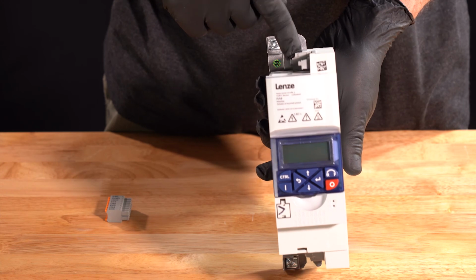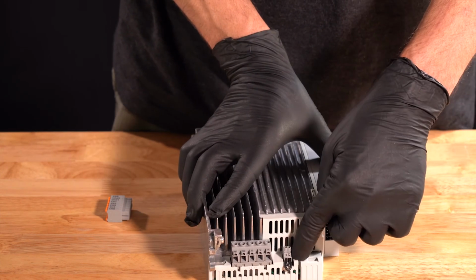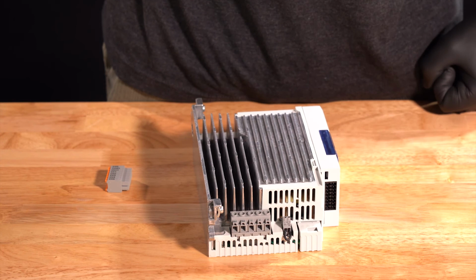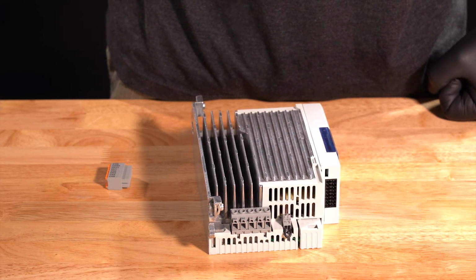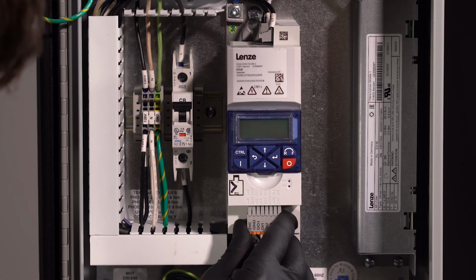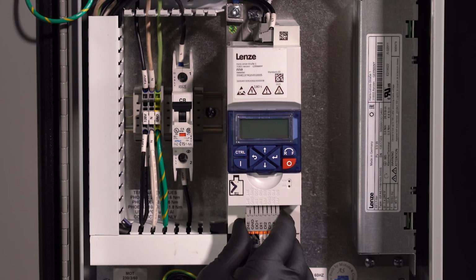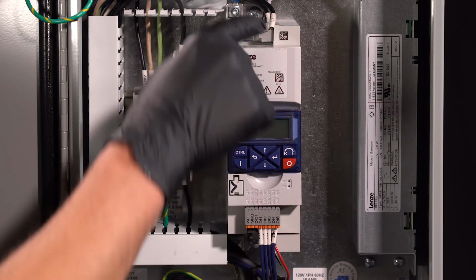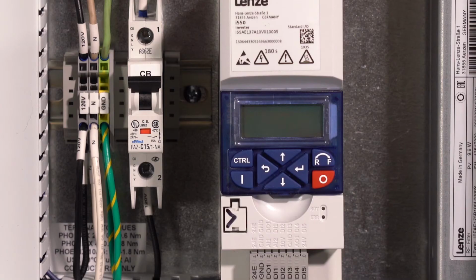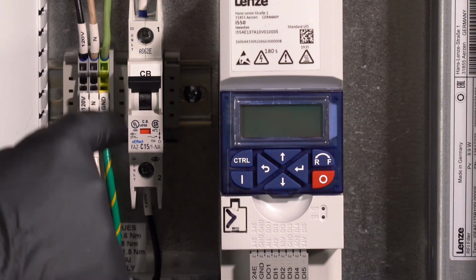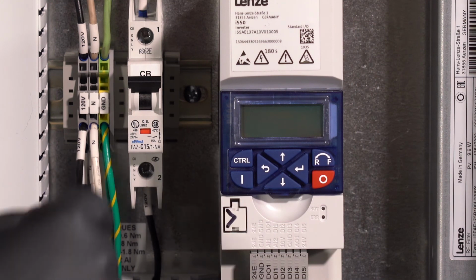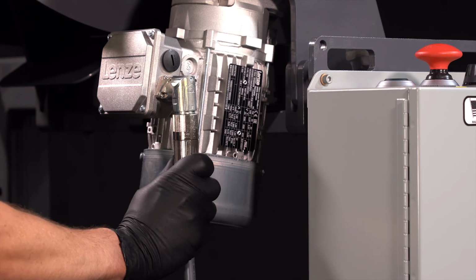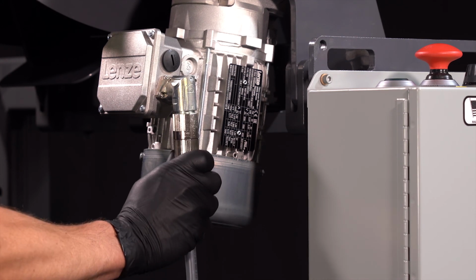Keep in mind that the jumper on the bottom of the VFD will need to remain in place in order for proper functionality. After mounting your new VFD into the panel, simply plug all the wires back in to the same locations from which they were removed. The proper orientation of the internal circuit breaker for the machine to have power is in the up position with the switch showing red. The electrical connection for the motor removes very simply with no tools.